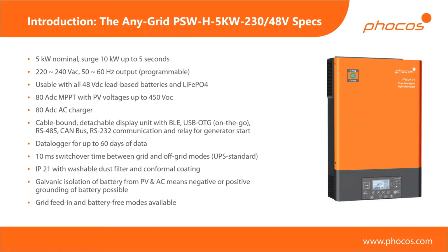So you might have a cottage, for example, where you go on vacation, and the inverter might be in a separate room connected to your batteries, and you want to see the battery level and all of the parameters from your living room, and like that, you can just pull a cable between the two. Otherwise, in the display unit, we also have Bluetooth Low Energy, so BLE. You can hook up to that, you'll see later, with an app. So if you're a little bit further away or you don't want to pull a cable, you can use the Bluetooth app as well.